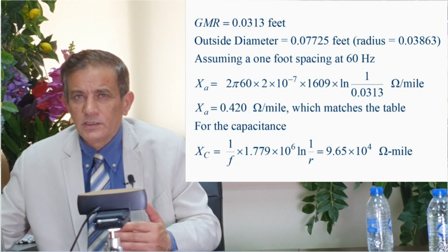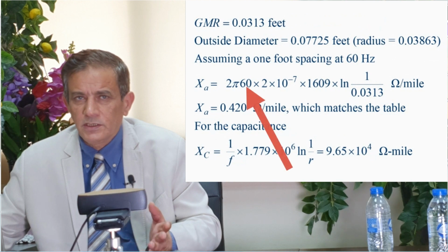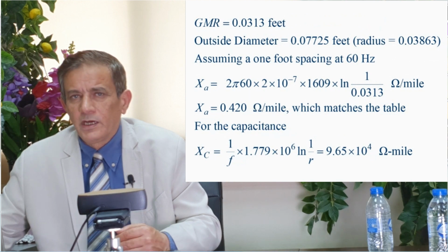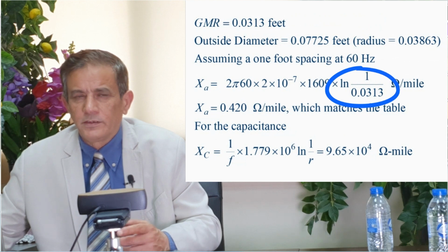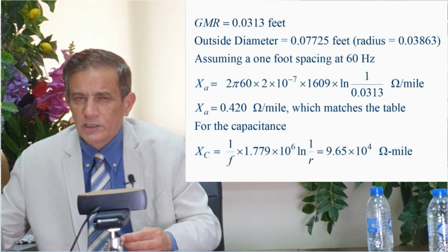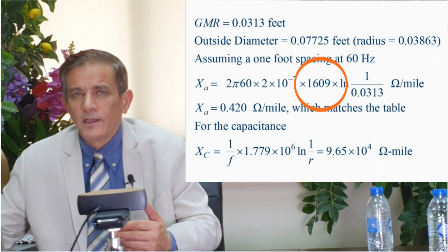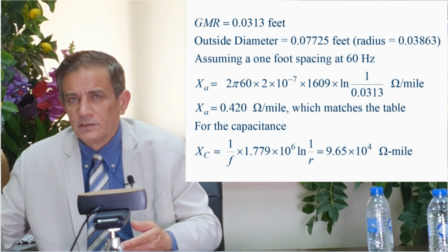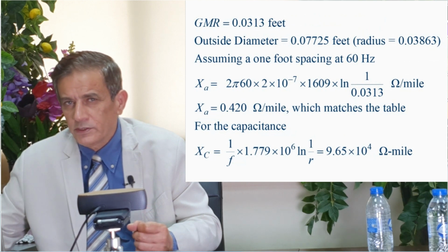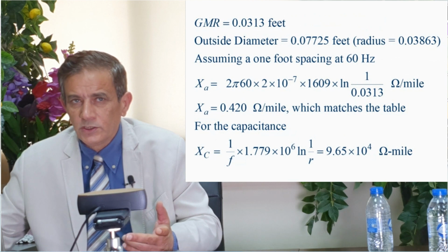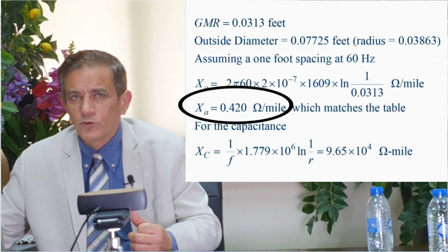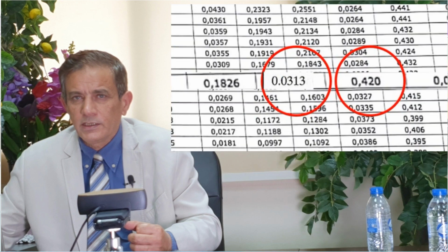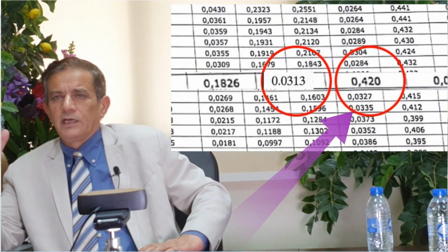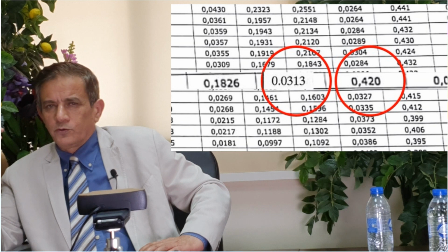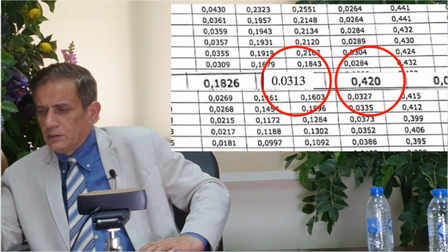Here, as in the question, the frequency is given as 60 Hertz, so XA is simply this equation: I substitute by dividing by 0.0313. We multiply by 1609 for the conversion to per mile, since each mile has 1609 meters. If you do this, XA will be 0.42. Go back and check it with the table, you find it the same, the circuit on the right, 0.42. Is it clear now?